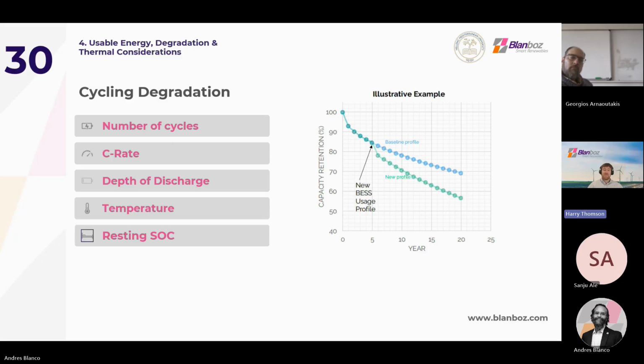Temperature and the resting state of charge. As before with calendar aging, these factors also increase the rate of cycling degradation, not only the calendar. And just for the benefit of time, I'll refer to my previous reasoning. We recommend our developers use flexible warranties that take into account the actual use of the BESS, and we can see this here. Each year, the battery is being compared to the baseline depending on the actual use of the batteries.